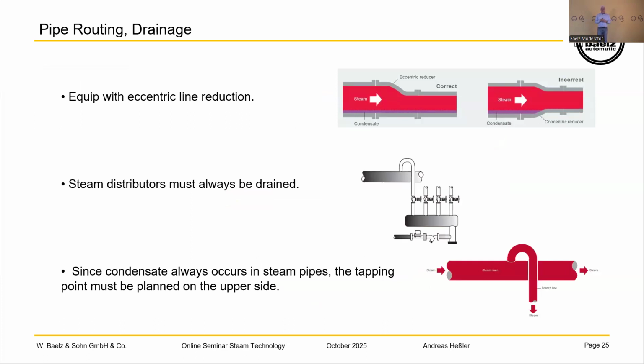Let's have the next slide on the top. You see that we always prefer an eccentric to a concentric pipe reduction. You see it in the picture, of course. When you have a concentric reduction, water or condensate can stay there and cause hammering on the steam pipe. So it would be better to have an eccentric reduction. Steam distributors must always be drained, that's for sure.